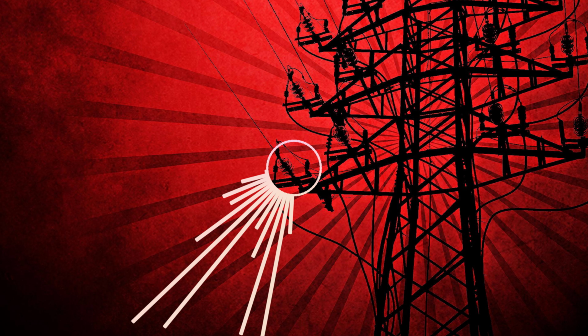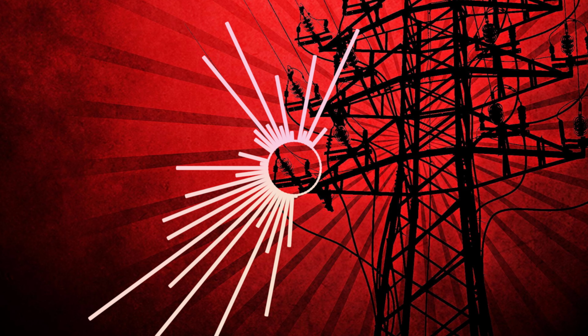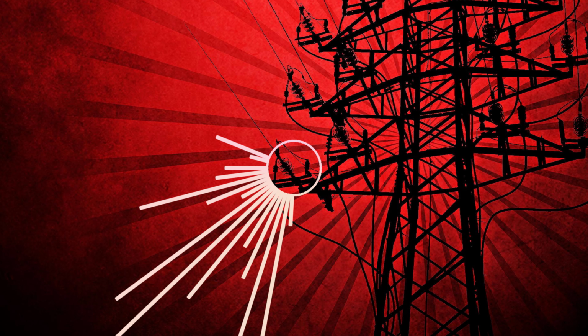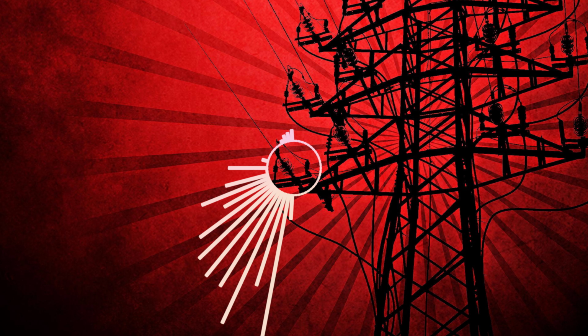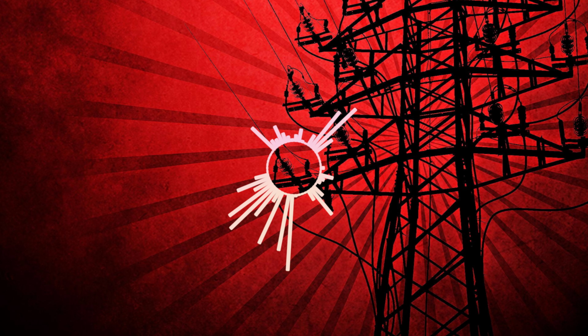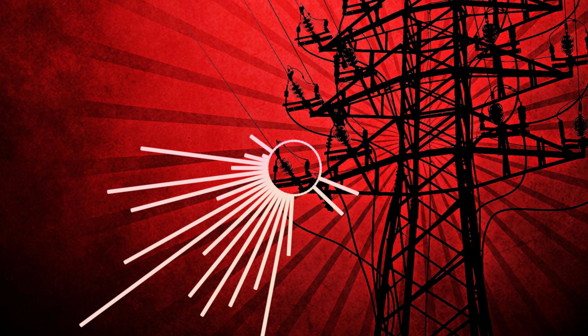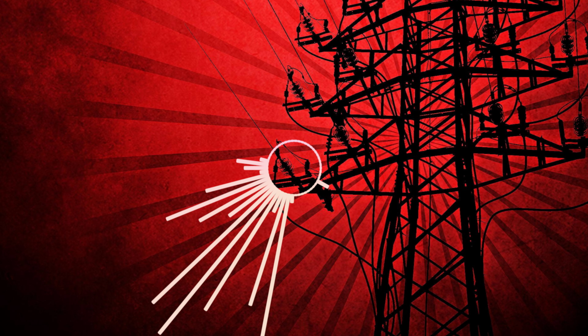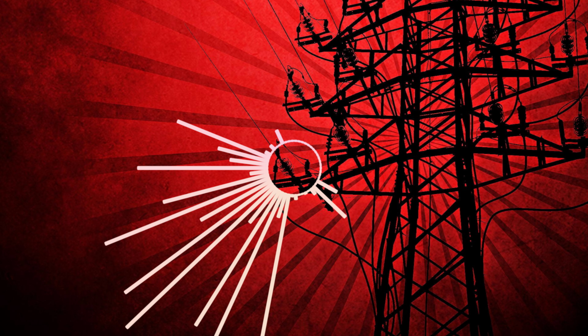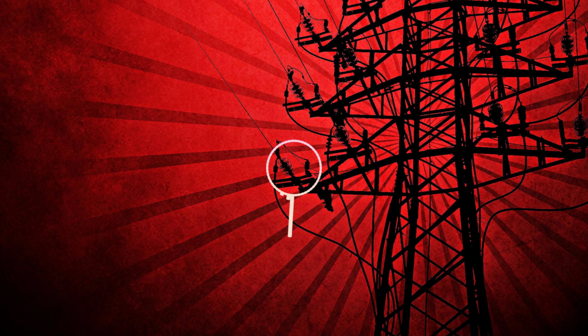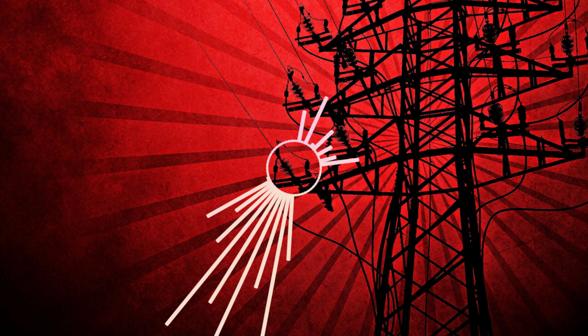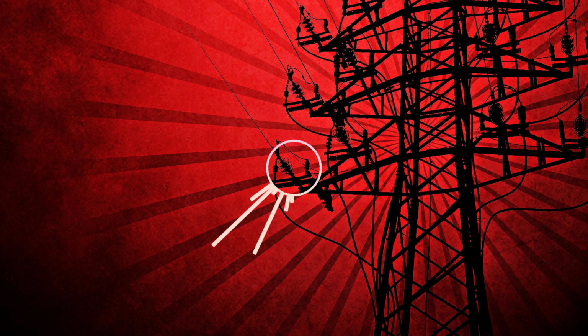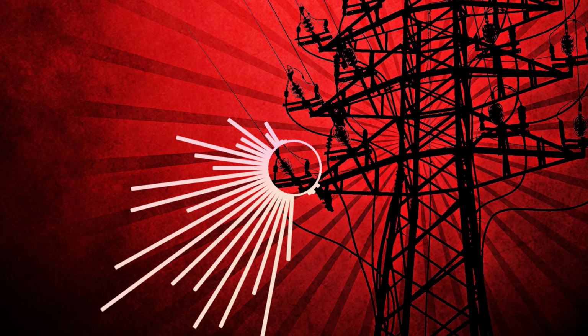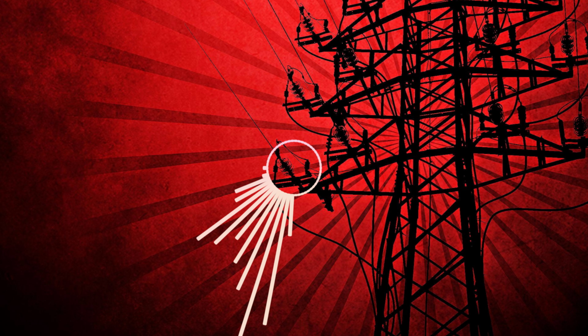Let's walk through a real-world scenario. You're an apprentice working on a commercial building. A new 500 kilowatt transformer is installed to replace an older 300 kilowatt unit. Sounds like an upgrade, right? But with the bigger transformer, the available fault current at the main panel jumps from 22,000 amps to 36,000 amps. The original panel still says 22,000 amps.